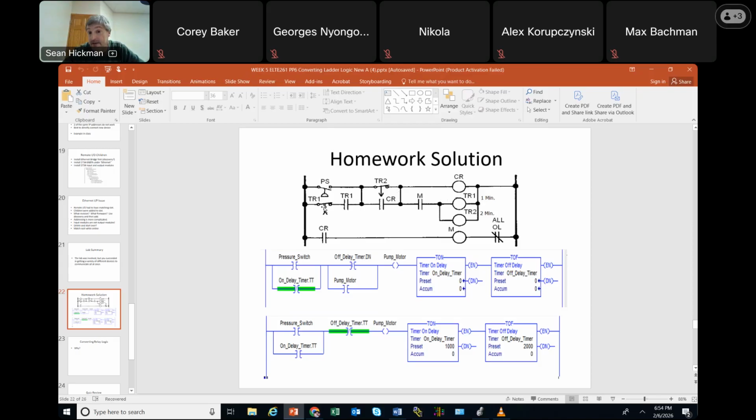And then it kind of locks it. It runs for 1 minute here, and then boom, that pops open, killing all the memory. And then hopefully after a minute, any type of backflow or preventer, check valves or pressure or anything like that is all stabilized, and then we're ready to run this again when we need to. Okay, and then after 2 minutes, when this one resets, then your system can run again. So it's 1 minute to converge on a solution, and everybody's happy, and there's no jumping around of my sensor here. And then after 2 minutes, everything's primed again.